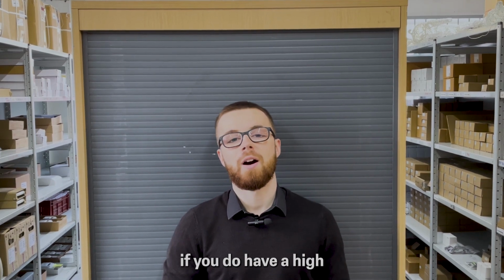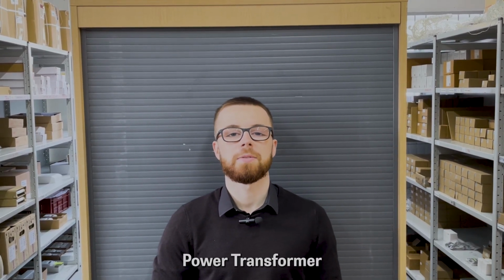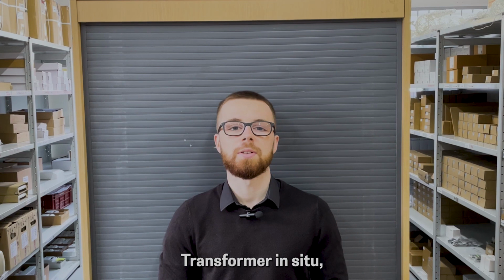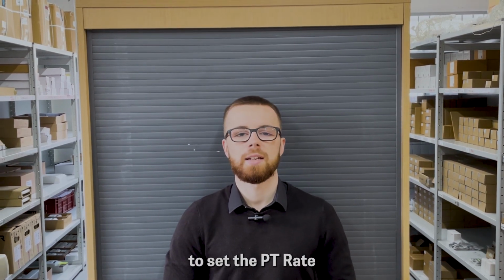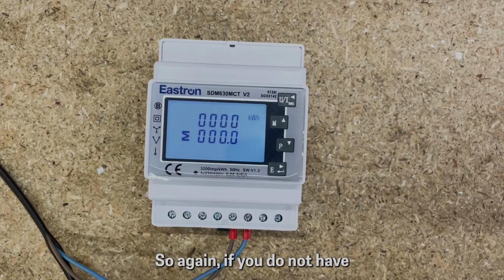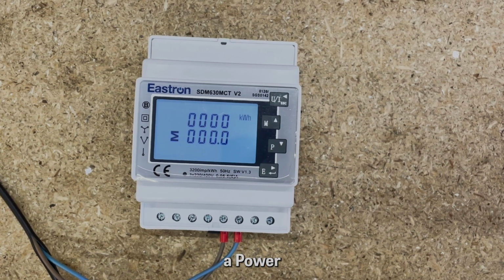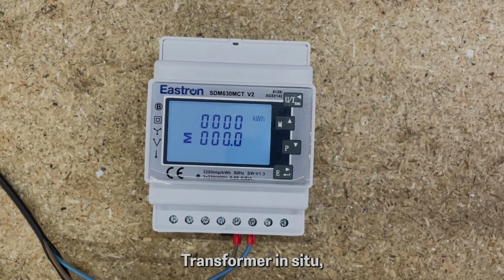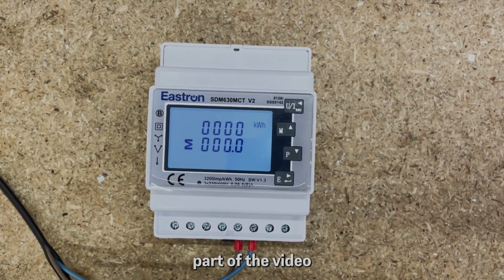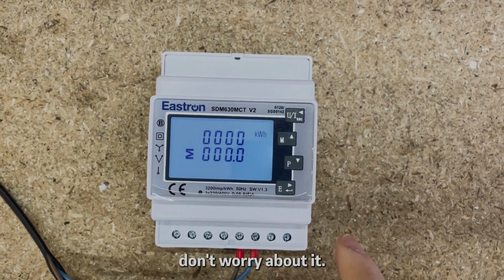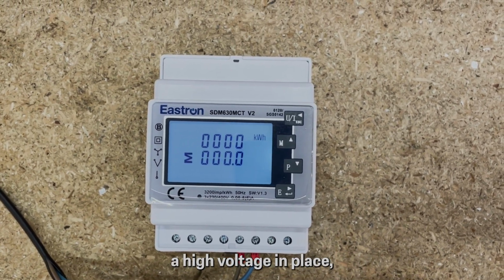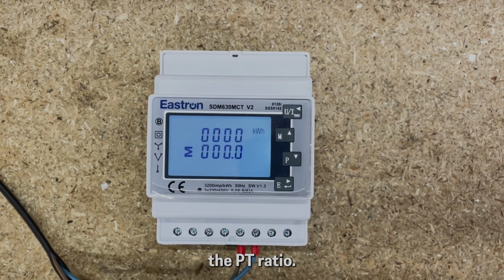However, if you do have a high voltage supply and you've got a power transformer or a voltage transformer in situ, then you do need to set the PT rate, and this is how you do so. So again, if you do not have a power transformer or voltage transformer in situ, then this part of the video is not for you, so please don't worry about it. But if you do have a high voltage in place, then this is how you set the PT ratio.